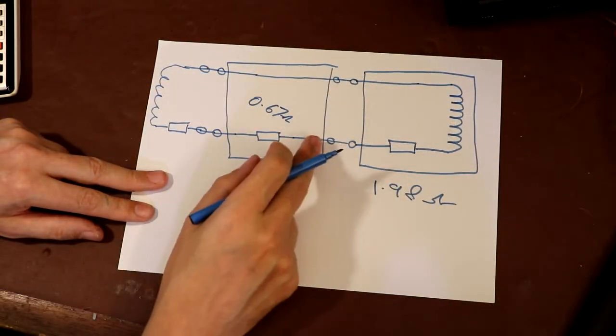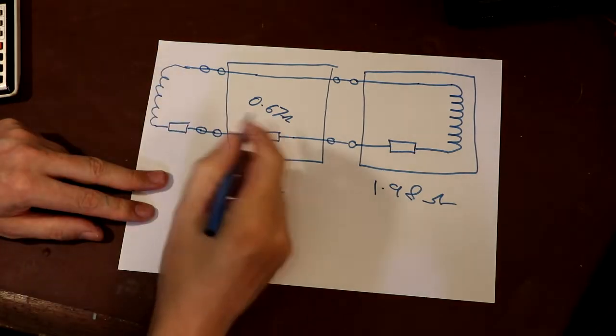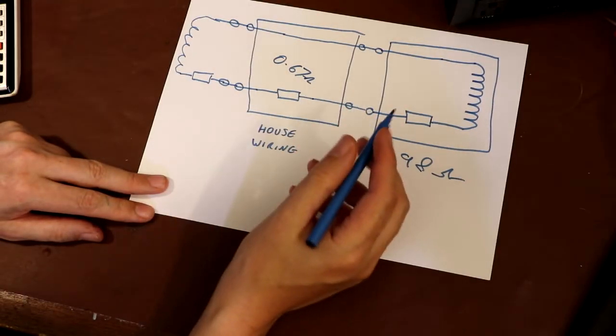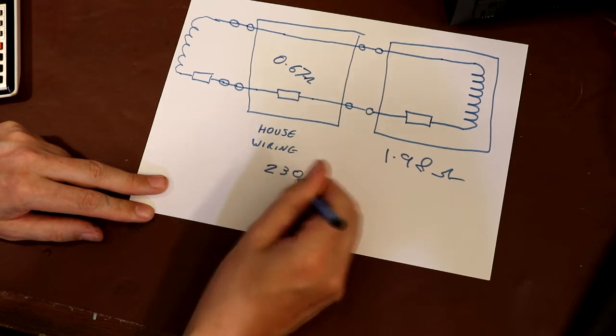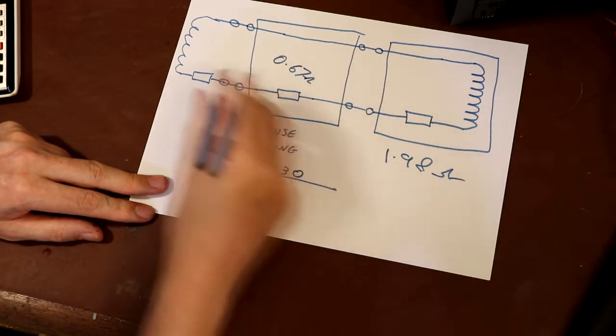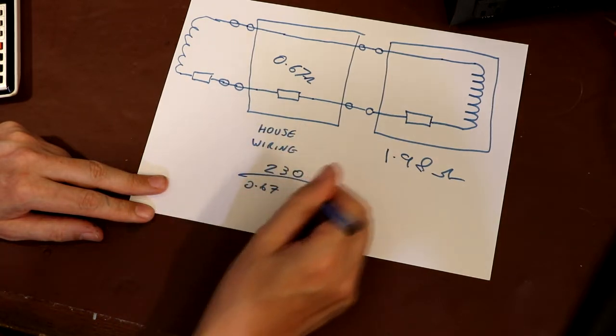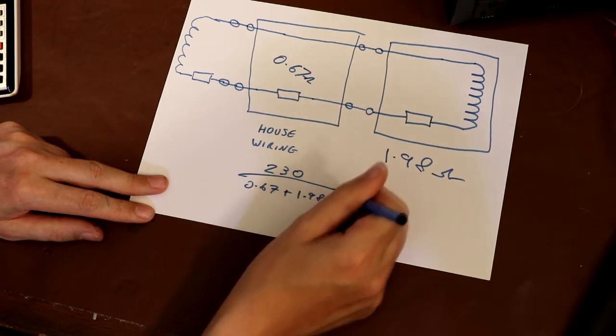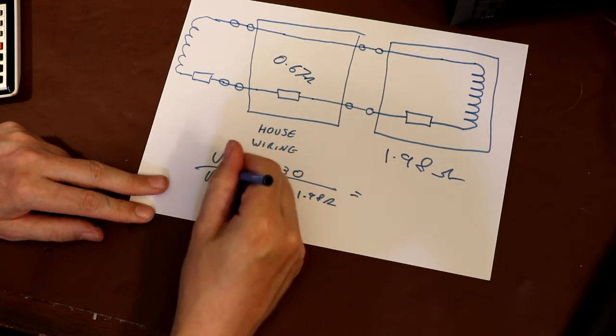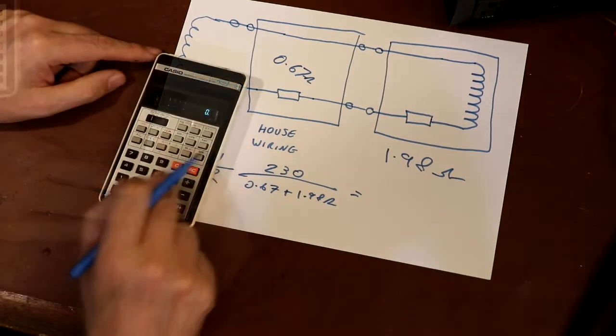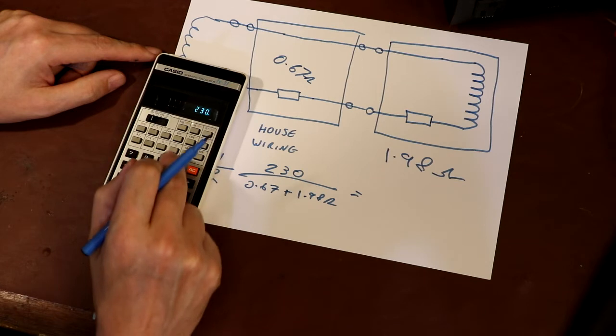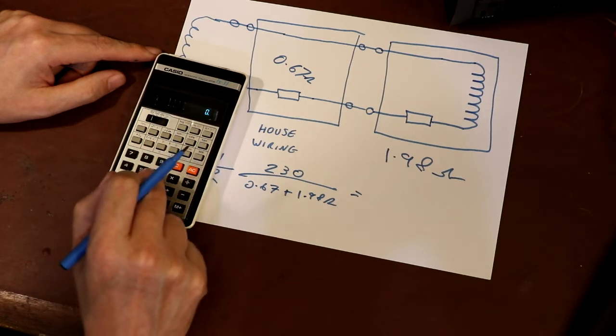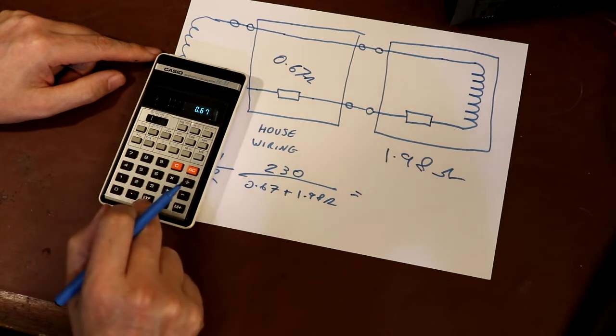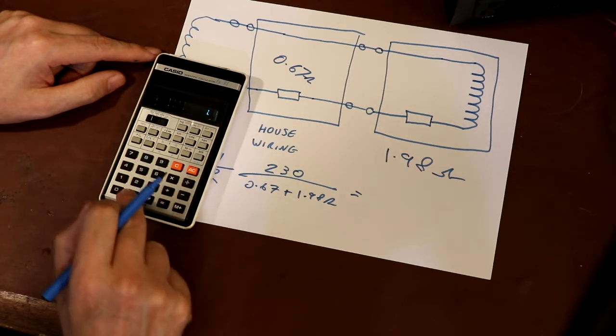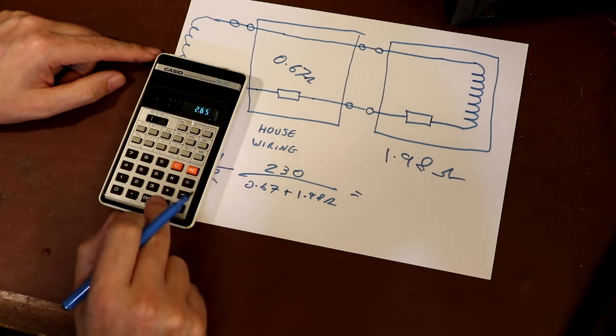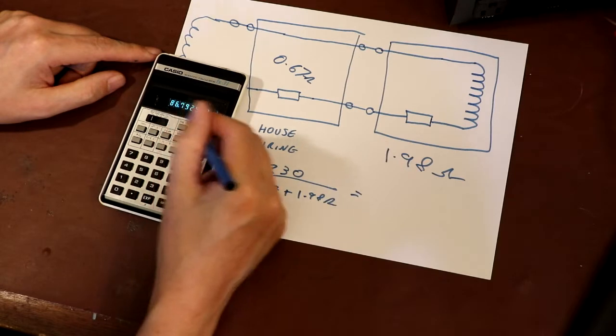And the way that I'm going to try to calculate the peak current now is to very crudely use Ohm's law. So our nominal supply voltage is around 230. What we're going to do is take our 0.67 and add that to 1.98 ohms. So we're just doing V over R equals I. 230 divided by 0.67 plus 1.98 equals 86.79.